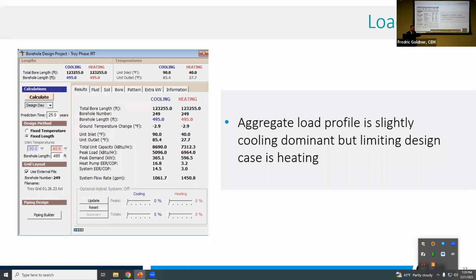Nowhere in the model did we see a diversity where cooling may be picked up and we can now re-inject that heat during the summer months so that we wouldn't have that gradual cooling. So I'm hearing normally you do 8760 hours per year, but actually you're doing a lot more than that. I'm doing 20 years to see, oh yeah.